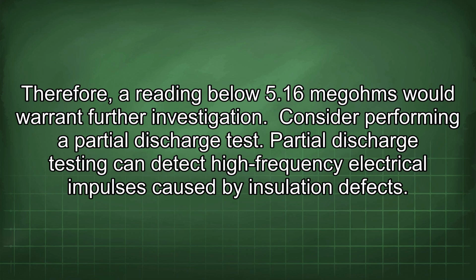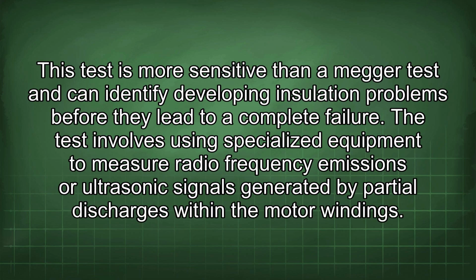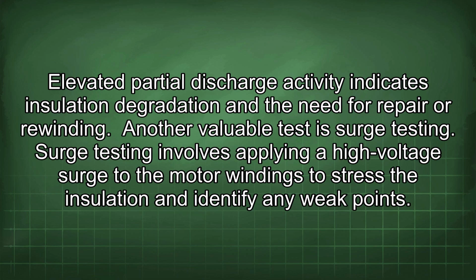Consider performing a partial discharge test. Partial discharge testing can detect high-frequency electrical impulses caused by insulation defects. This test is more sensitive than a megger test and can identify developing insulation problems before they lead to a complete failure. The test involves using specialized equipment to measure radio frequency emissions or ultrasonic signals generated by partial discharges within the motor windings. Elevated partial discharge activity indicates insulation degradation and the need for repair or rewinding.